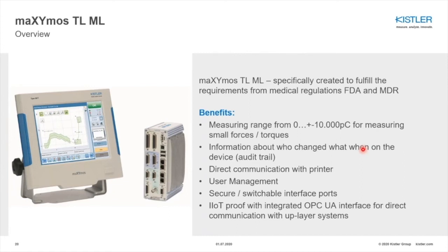Sometimes it's necessary that you communicate directly with a printer, and the maXYmos TL ML is able to communicate with the printer and print out directly the results of your actual measurement. Also possible with the device is user management, giving different rights to the users of the maXYmos TL ML. Also, you can switch on or off interface ports. For example, the device itself has a USB port, and if it's not allowed to use USB sticks in your manufacturing, then you can switch off this USB port, and this functionality can be handled by dedicated users. And last but not least, the device is also IoT proof. So we integrated the OPC UA connection so that you can communicate directly with upper layer systems.